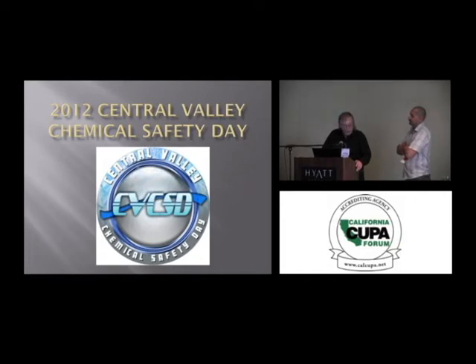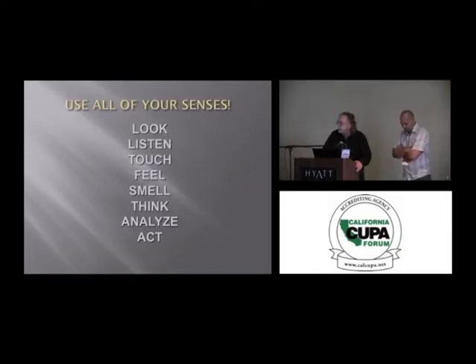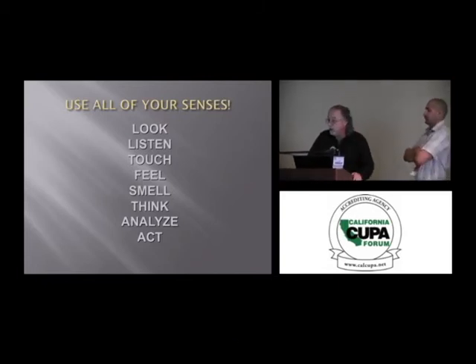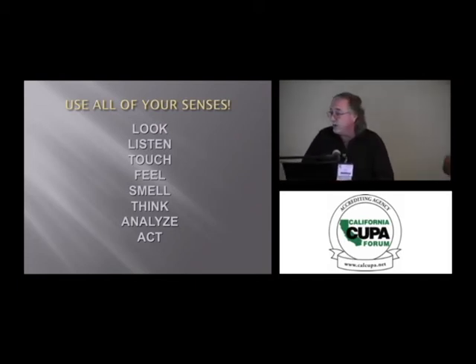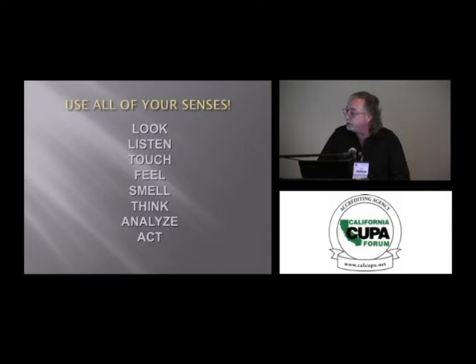When you're out there walking the plants, everybody, use all your senses. Look, listen to things, touch things, always use your nose. A little odor isn't a bad thing. If you had a perfect system and it was newer equipment, you might not get any odor. But there are some places you are going to pick up some odor, such as shaft seals at compressors, ammonia pumps, you might get a little bit of odor. Seals weep a little bit, and it's just a normal thing in our industry. But it shouldn't be to the point where the site's complaining. It shouldn't be anything that is more than just a slight irritation to you.